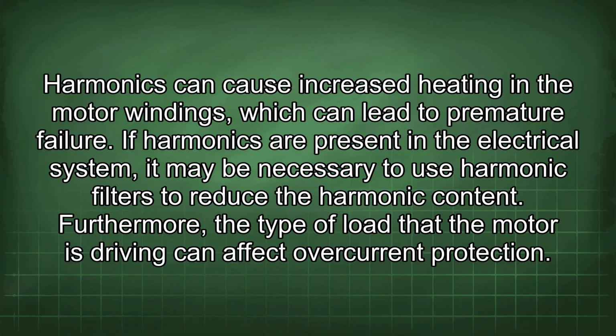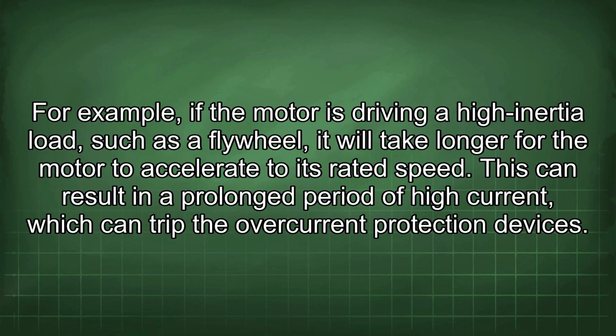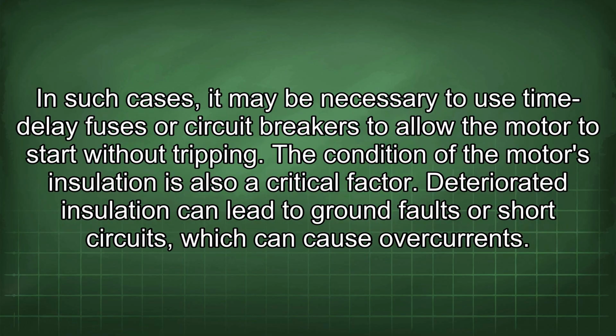Furthermore, the type of load that the motor is driving can affect overcurrent protection. For example, if the motor is driving a high inertia load, such as a flywheel, it will take longer for the motor to accelerate to its rated speed. This can result in a prolonged period of high current, which can trip the overcurrent protection devices. In such cases, it may be necessary to use time delay fuses or circuit breakers to allow the motor to start without tripping.